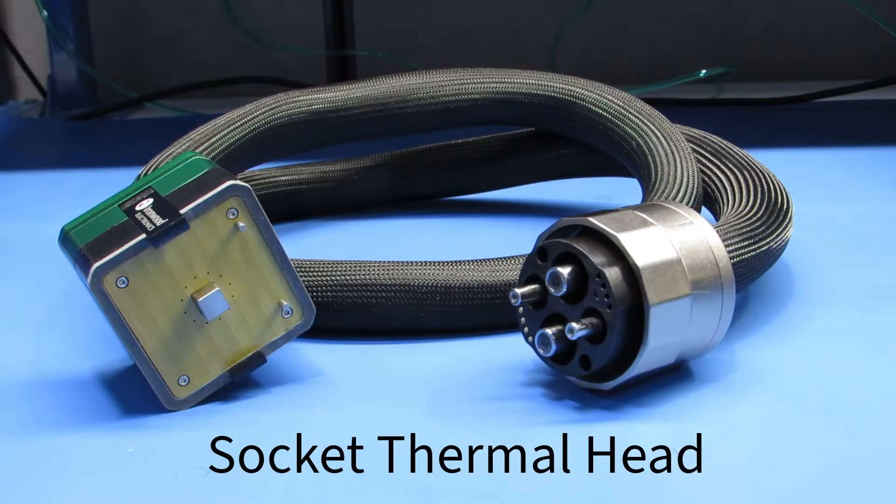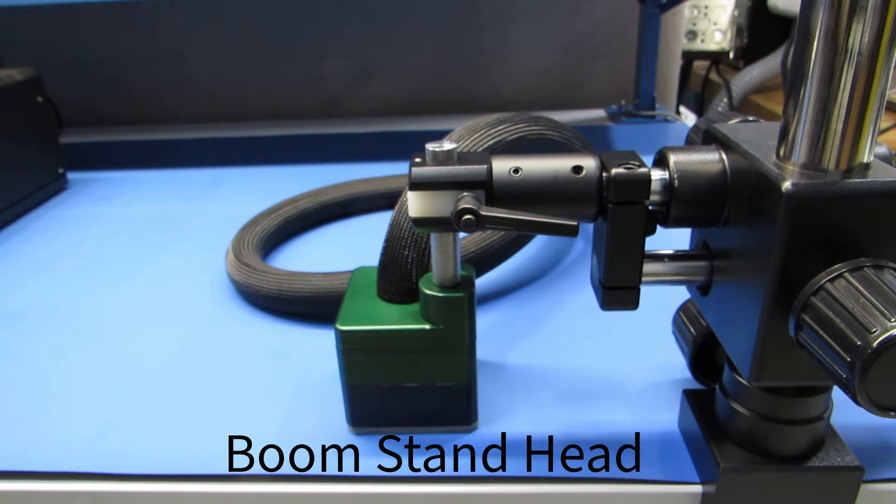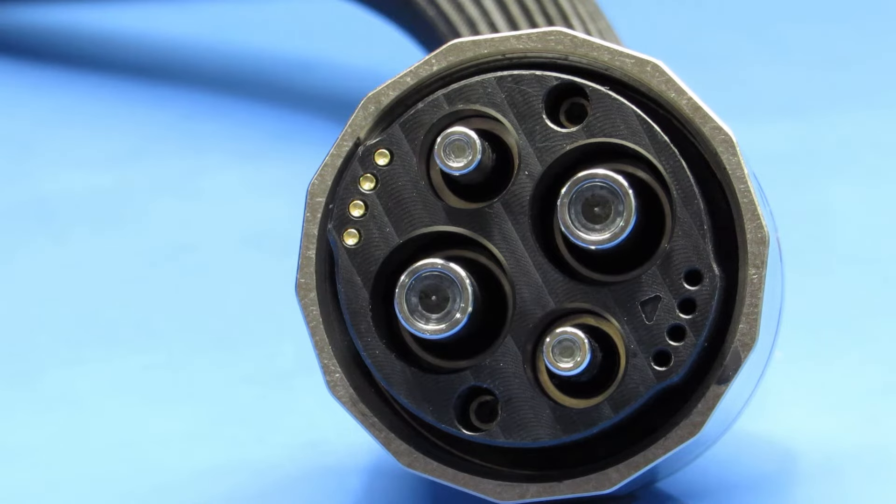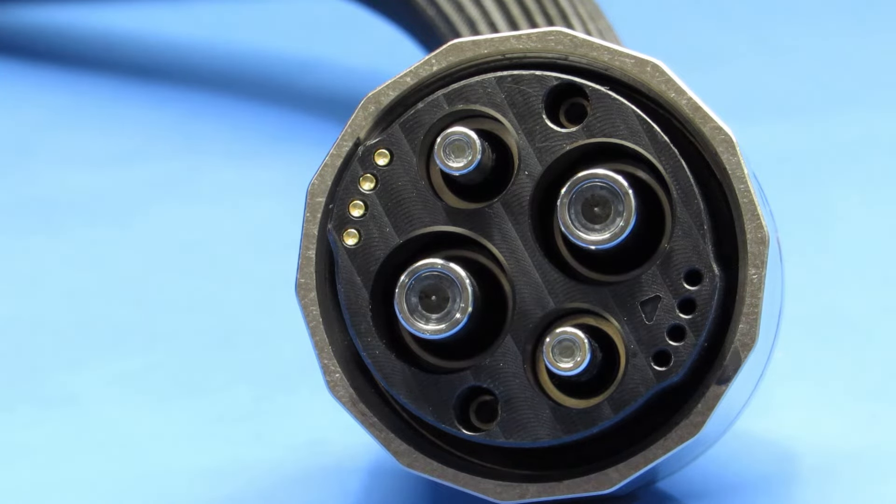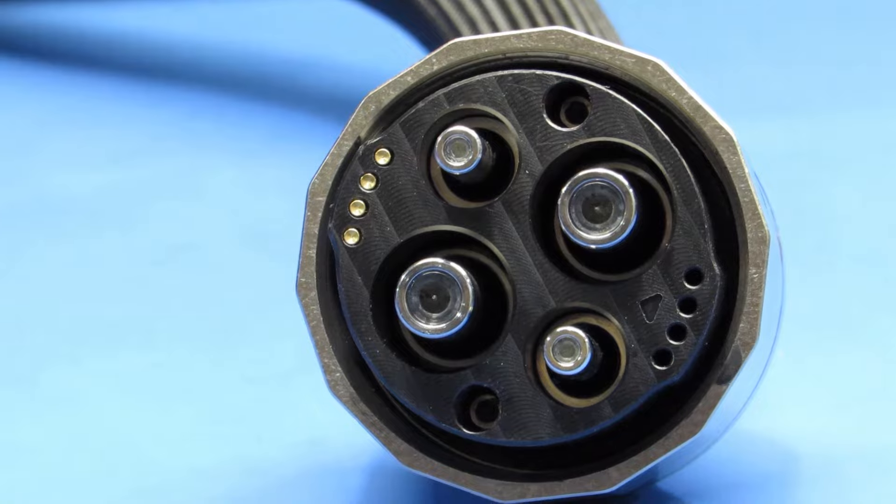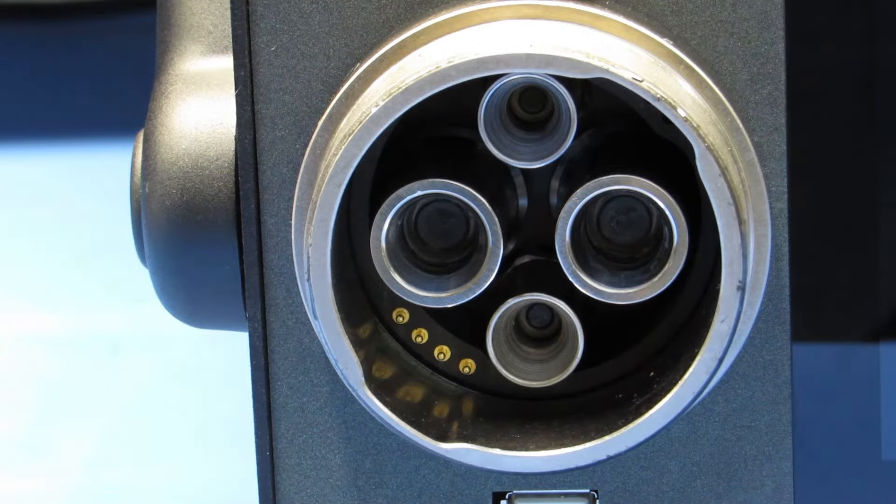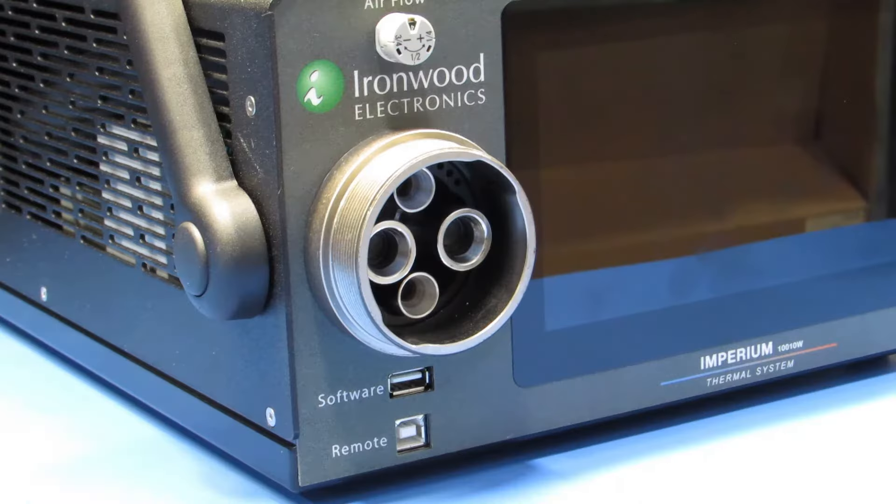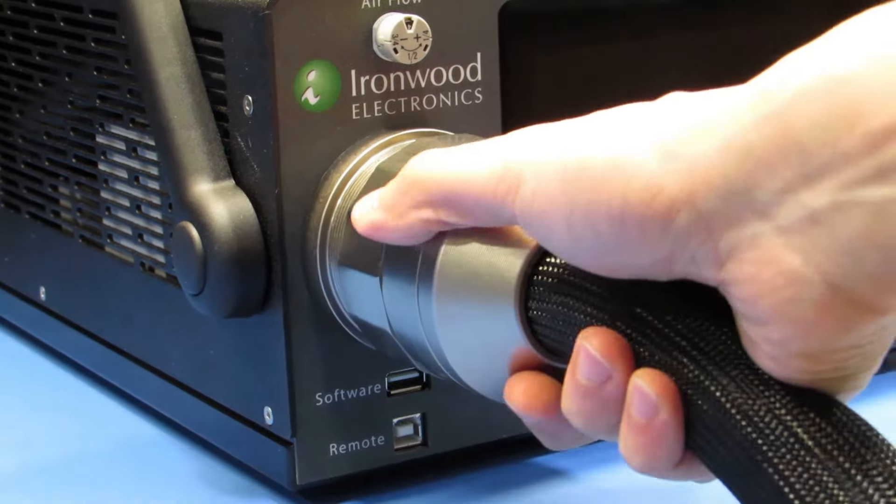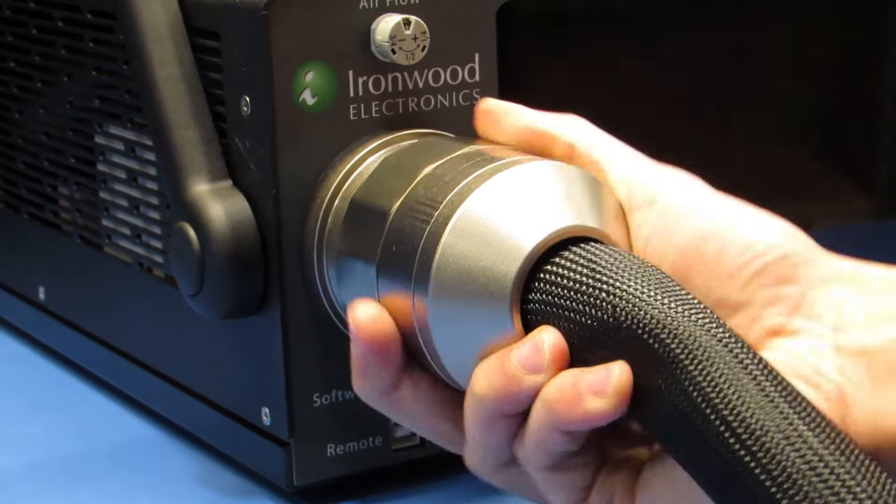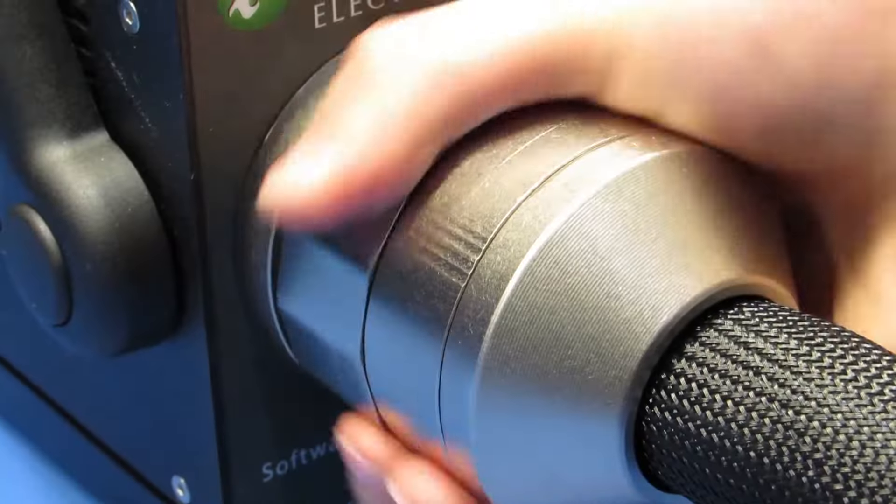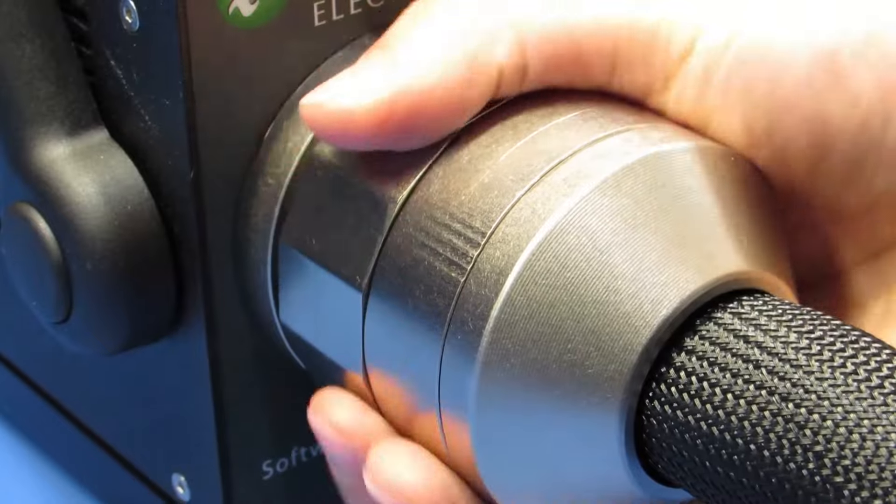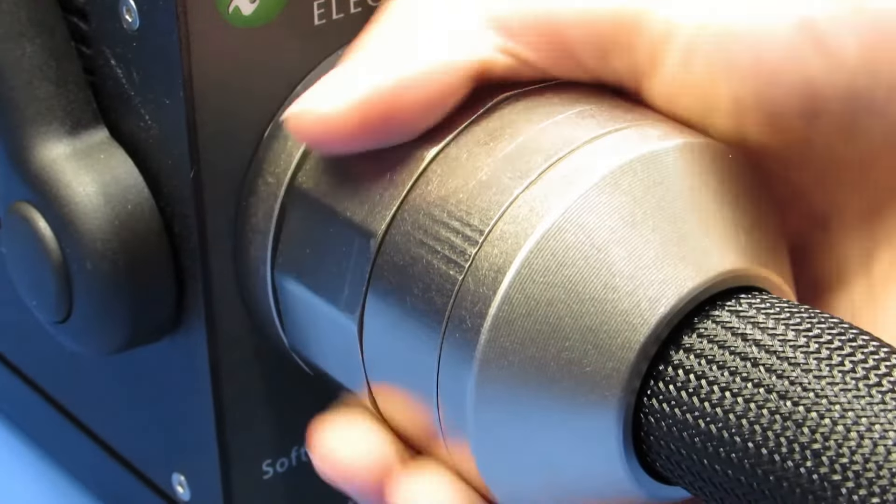Connect the thermal head connection with the appropriate thermal head for your socket or application. This connection is keyed to only go on one way. The four gold contacts on the male and female will be aligned. Slight pressure is needed to start the thread. Screw down the thermal head coupling nut until it comes to a stop. Do not over-tighten this connection.